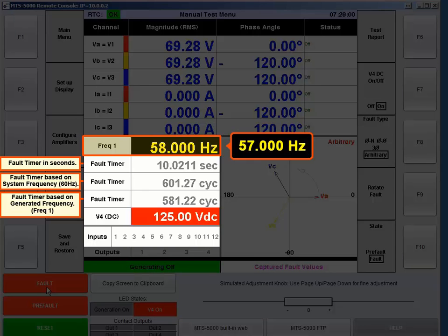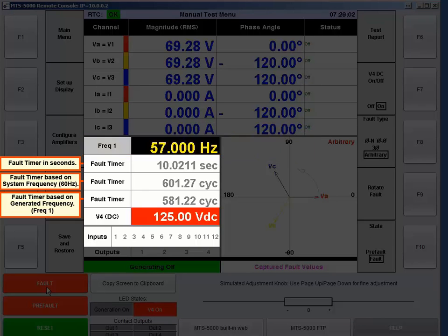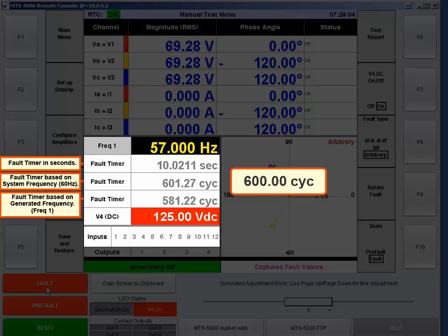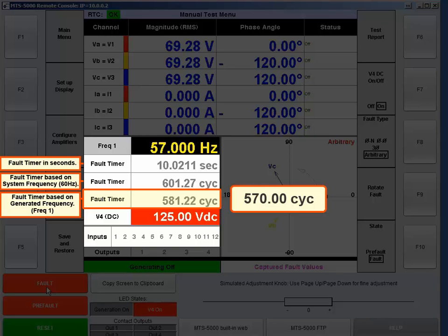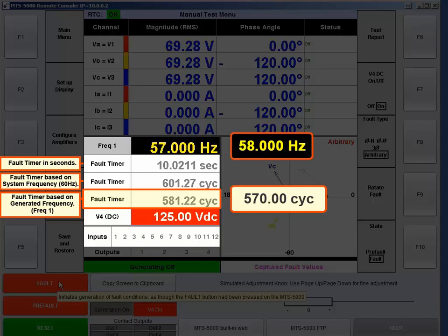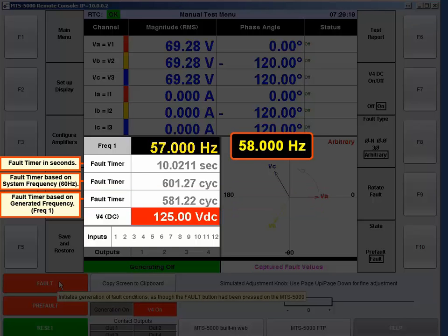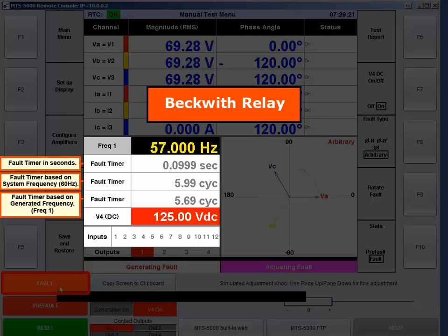Now I'm going to change the frequency to 57 Hz. If this relay is basing its 600 cycles on the system frequency, we shouldn't notice a change in the time in seconds at all — except in that bottom fault timer, which should be closer to 570 cycles instead of 580, because the 580 was based on 58 Hz.